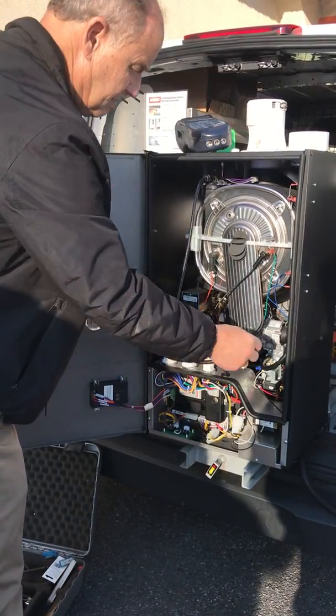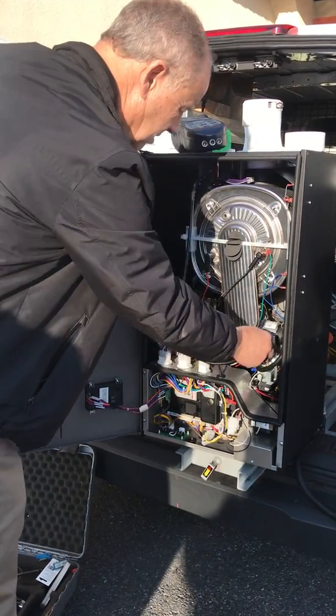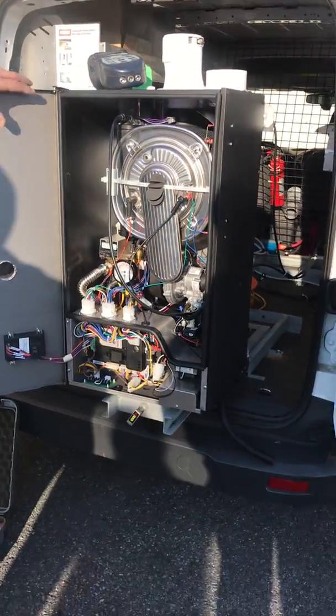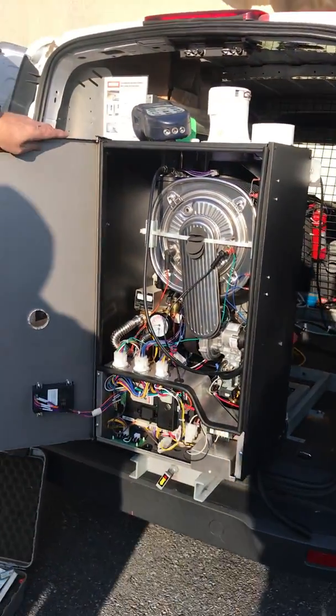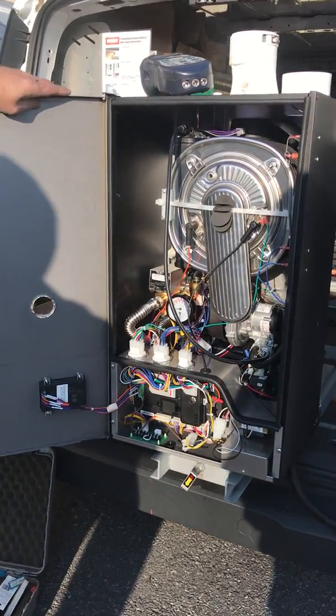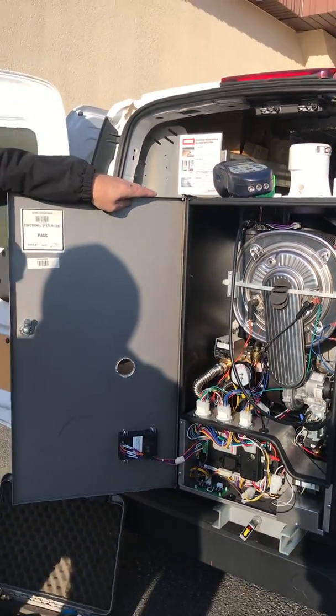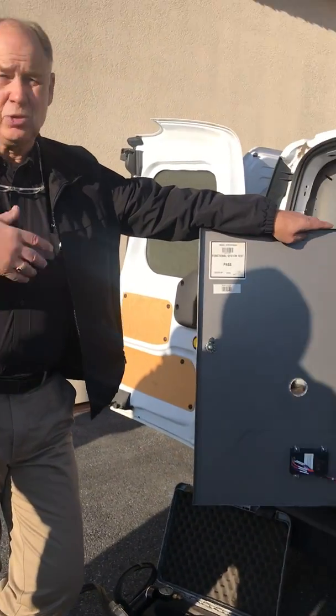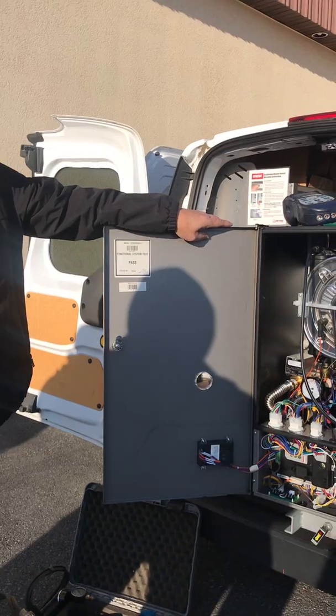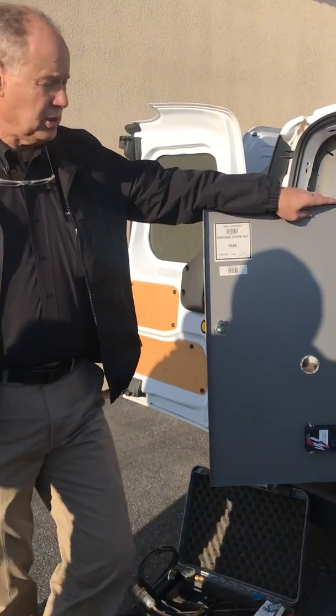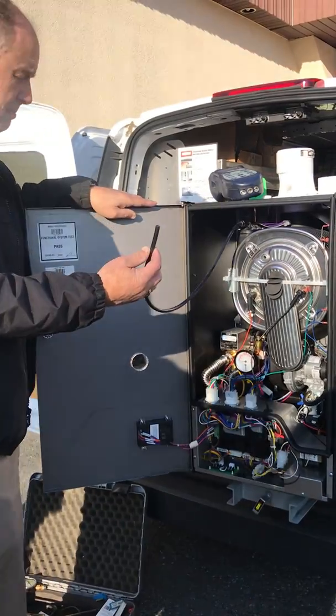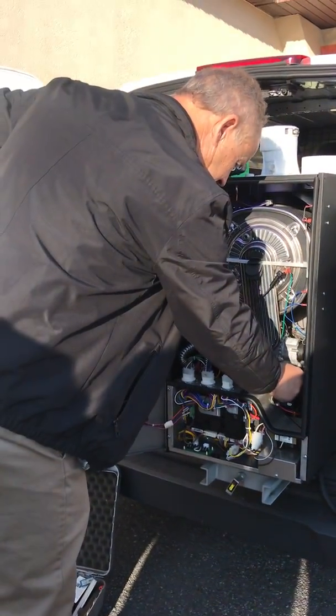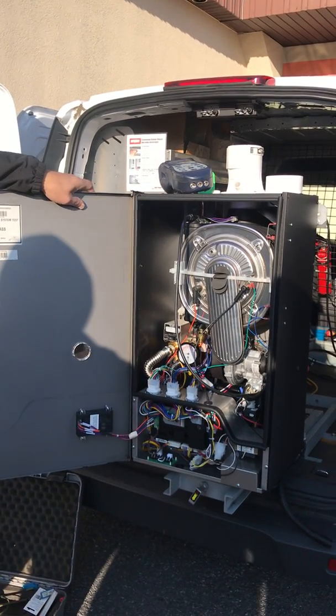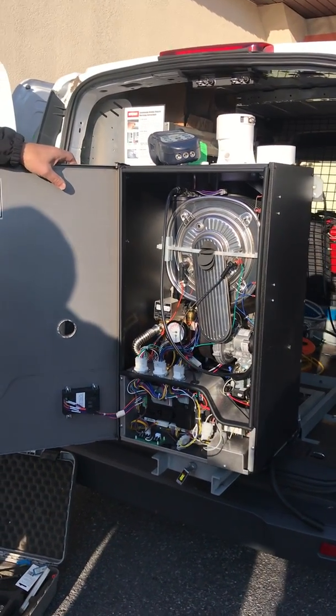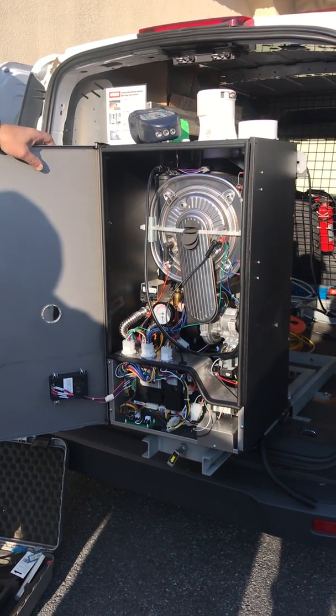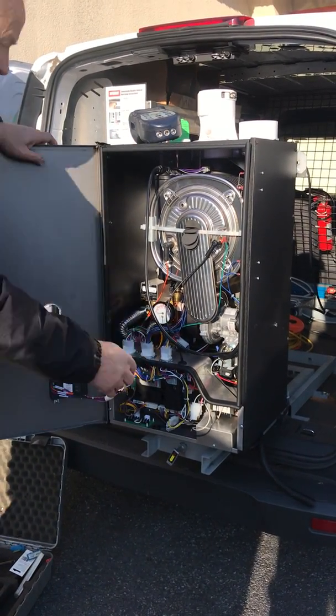We had a guy down in Maryland. This hose, where the heck? Oh, that goes on here. So he stuck it right on there. And that actually bleeds the air. As the regulator opens, you got to vent the air off the top. Yeah. So when he did that, it wouldn't vent the air off. So they're talking to him on the phone, going through. Nobody can figure out what's wrong with this boiler. So they said, okay, give you a new boiler. So he puts a new boiler in. That's the same thing? Damn, this hose, second time. So he sticks it on there. Hey, that boiler's doing the same daggone thing. Finally, somebody went out to the job and realized he put the hose on and blocked off his regulator. So this does not go on there.